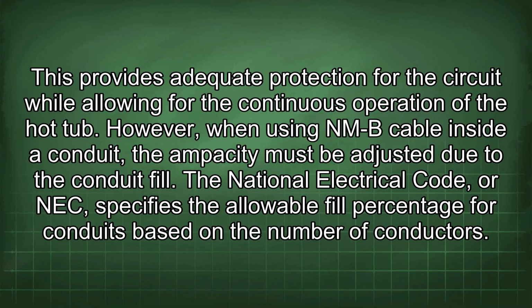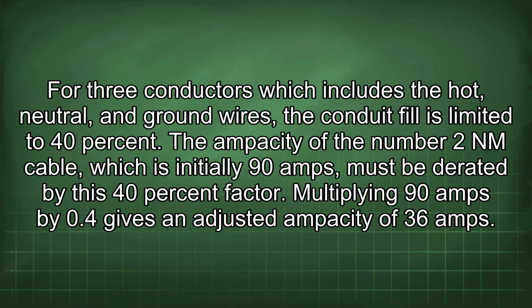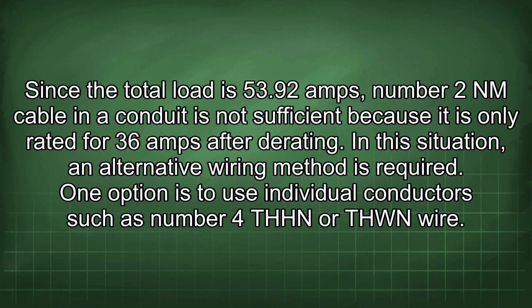However, when using an NM cable inside a conduit, the ampacity must be adjusted due to the conduit fill. The National Electrical Code, or NEC, specifies the allowable fill percentage for conduits based on the number of conductors. For 3 conductors, which includes the hot, neutral, and ground wires, the conduit fill is limited to 40%. The ampacity of the number 2 NM cable, which is initially 90 amps, must be derated by this 40% factor. Multiplying 90 amps by 0.4 gives an adjusted ampacity of 36 amps. Since the total load is 53.92 amps, number 2 NM cable in a conduit is not sufficient because it is only rated for 36 amps after derating.